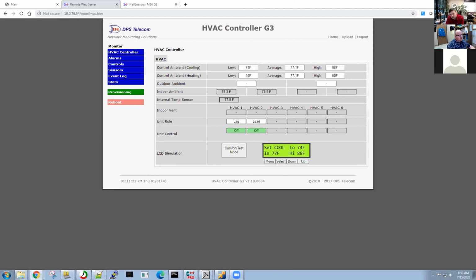You can see that we can have up to 6 HVACs configured on this unit. Currently only 2 are configured here: HVAC 1 and HVAC 2. Currently, HVAC 1 is in the lag role and HVAC 2 is in the lead role, and that's going to cycle through to distribute load between your different HVAC controllers. And that's on a user configurable time as well. You can configure whether they shift daily, weekly, or at some other interval.